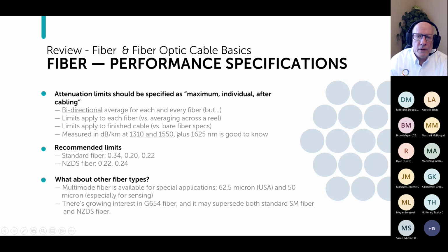And really, your benchmark is 1550. It's kind of the workhorse wavelength anyway. But not bad to measure at 1625. And if you're measuring at 1550, you can also measure at 1310. So, you might as well know those figures.